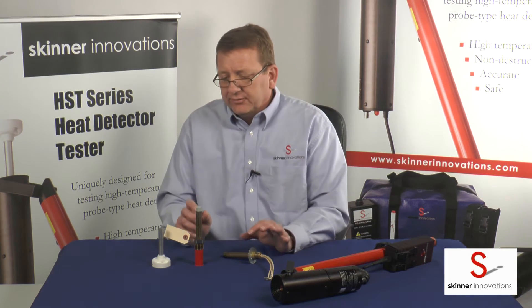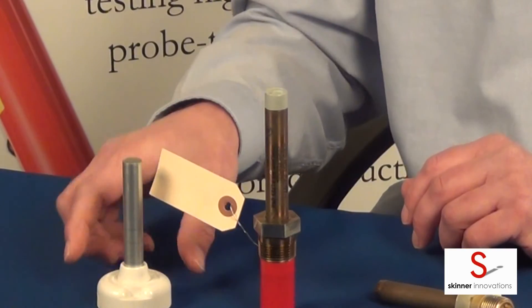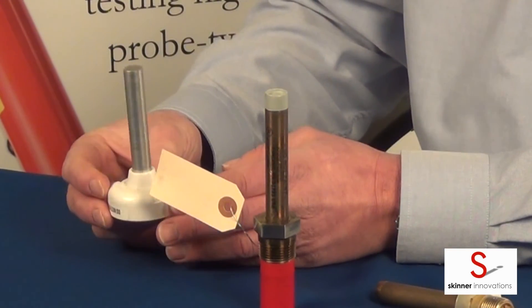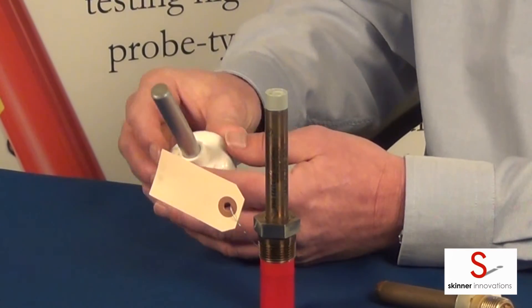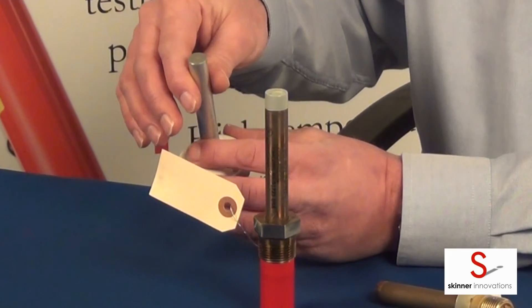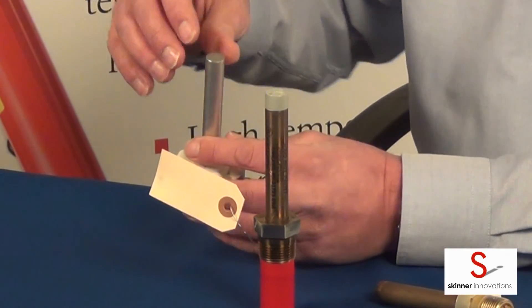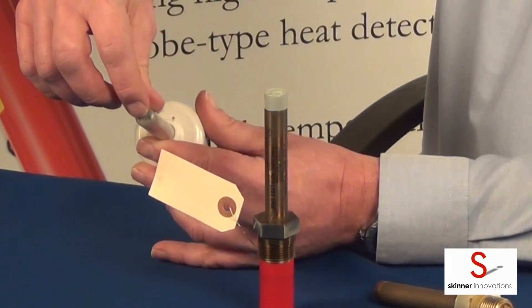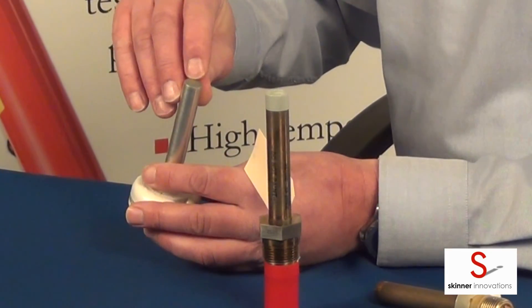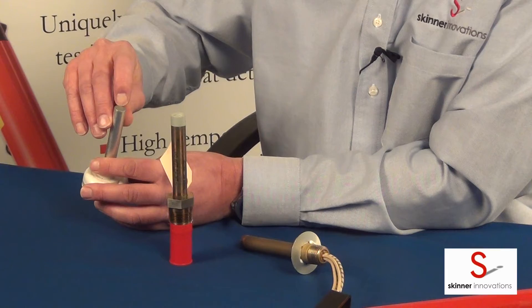Both these Fenwal detectors are 5/8 inch diameter detectors. Now the third detector is a Thermotech rate compensated detector. They are slightly smaller in diameter, and the way Thermotech marks their detectors is stamped right onto the end of the tube there on the end of the detector. It says 135, meaning this is a 135 degree detector.